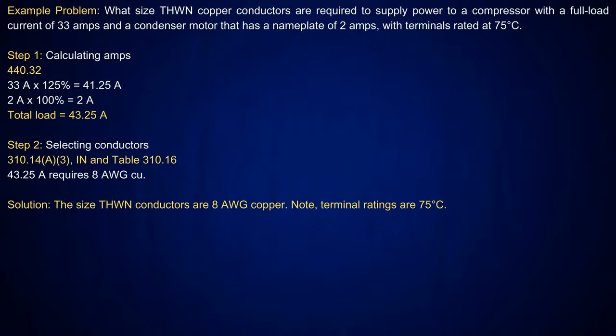Now, this one is where I'm dealing with an AC unit. Here I've got a compressor with a full load current of 33 amps, and then I've got a condenser that has a nameplate of 2 amps. I want to point out, you notice here we're saying nameplate. The reason is that when I'm calculating here and I look at Article 440, you're going to use the nameplate value, and I'm not going to use the motor value that's given in the tables.